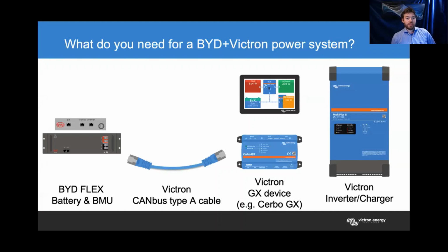As an overview, Victron is a power electronics company. We provide inverter chargers, charge controllers, and system control and monitoring components. The components coming from BYD are the BYD Flex and the separate BMU. You need one BMU per battery system — a single battery module requires a BMU, and a BMU can service up to 64 individual modules in the Flex range. You also need a Victron CAN bus Type A cable, which is the interface between the BMU on the BYD side and our Venus OS GX device on our side.